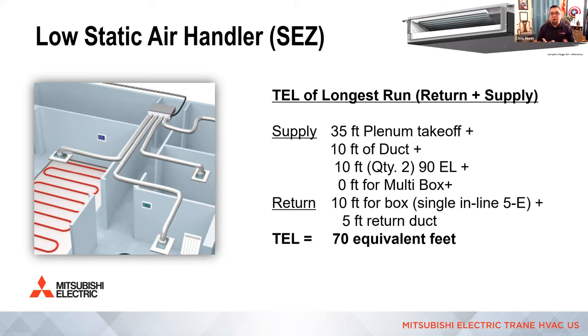So as an example here, if you just have a box, like the picture on the left-hand side on our low static air handlers, this is the most popular way to duct one of our low static air handlers, keeping the air straight with very little pressure loss and no balancing dampers, all right? This is not what you would normally do with mid-static or high-static air handlers. I want to make sure I'm clear on this.